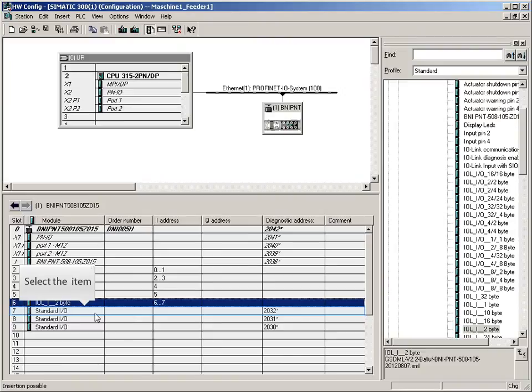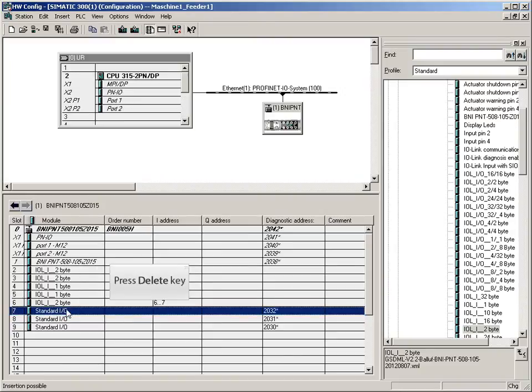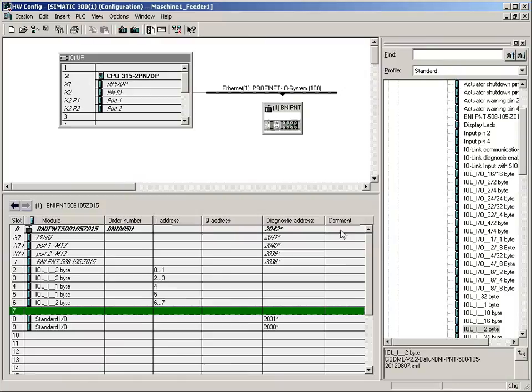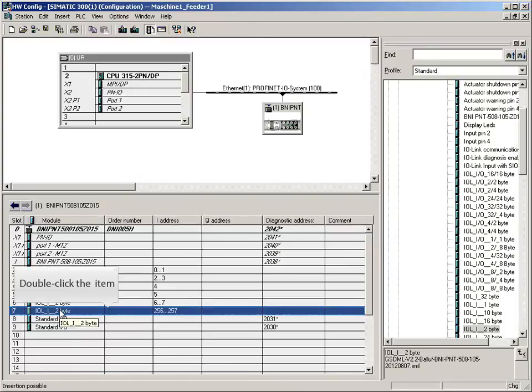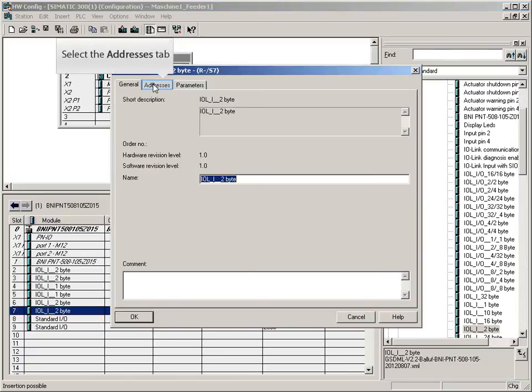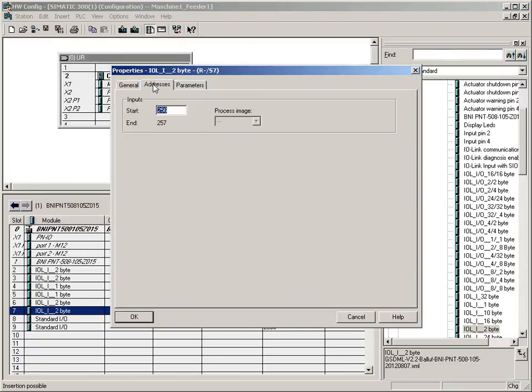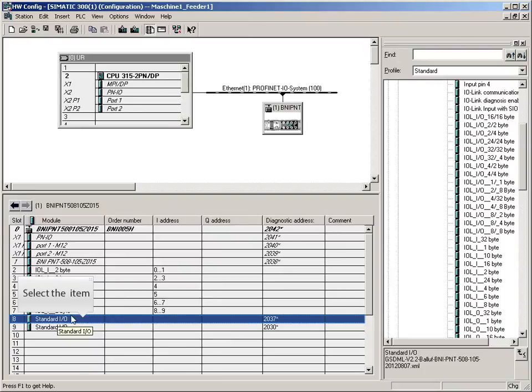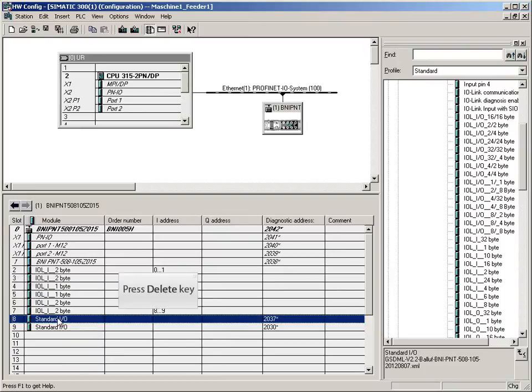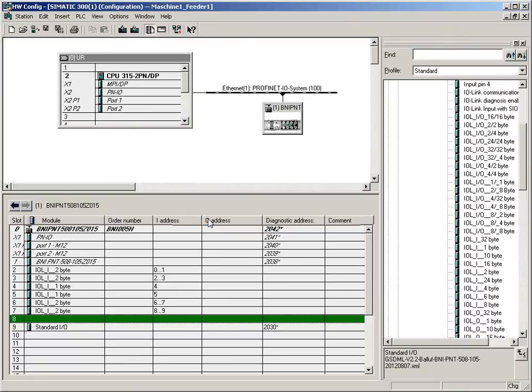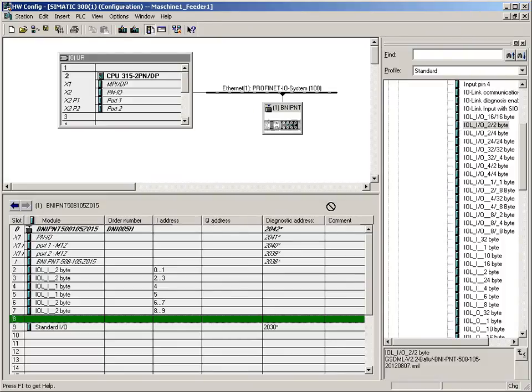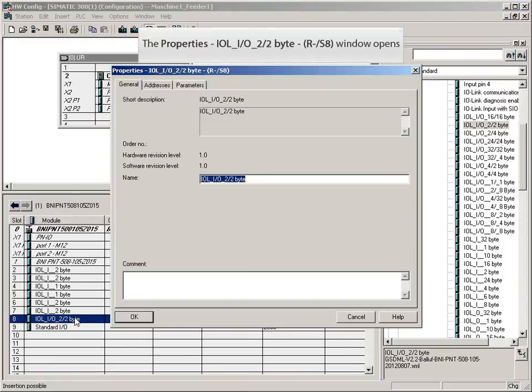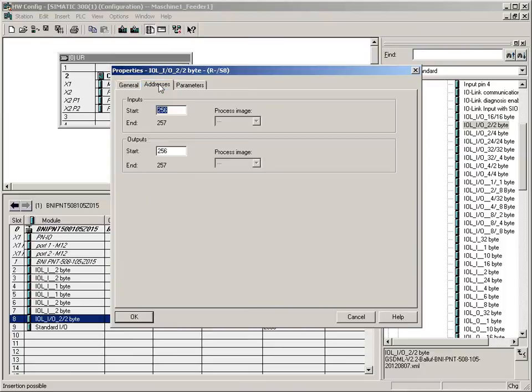Continue with address 6. Delete the current entry. Drag a module with two input bytes to this port. Continue with address 8. Delete the current entry. On this port, an IO link sensor hub is connected which needs two input bytes and two output bytes. Therefore drag the appropriate module to this port. Continue with address 10.